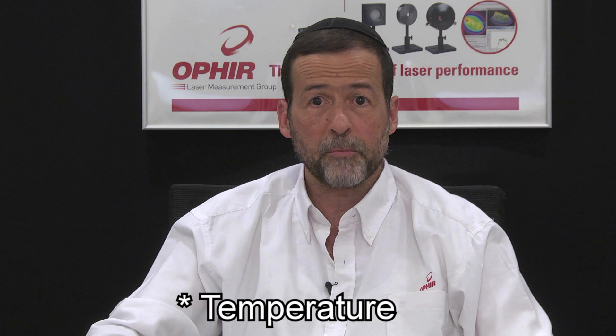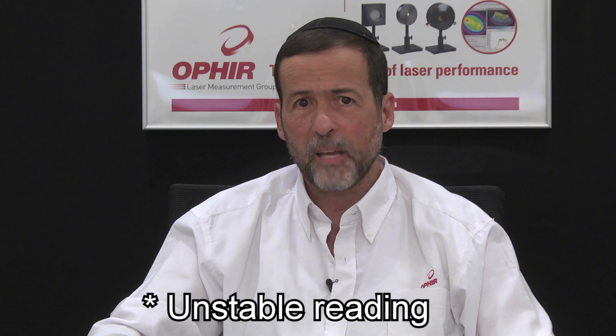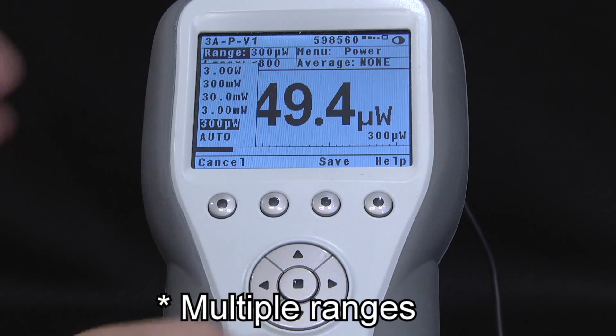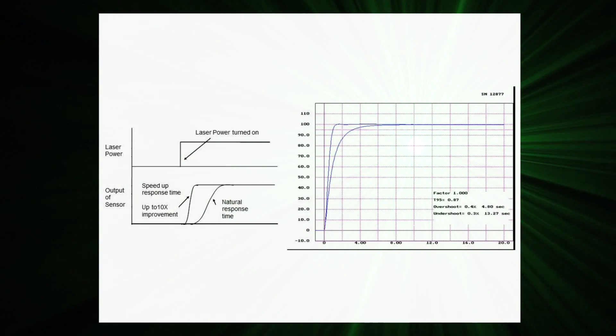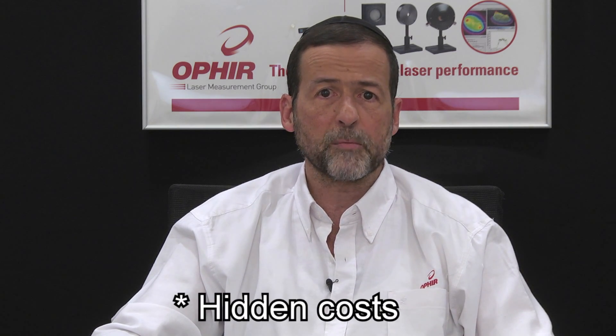The solution will have to correct for the photodiode's dependence on temperature and frequency. It'll have to account for batch-to-batch variations among the detectors themselves. What happens when the reading isn't stable? What about when you need to change gain in real time to give your sensor a useful dynamic range? For certain types of detectors, how about a speed-up algorithm to reduce the response time? Addressing these issues will involve costs, which, though not visible on a system BOM, are nevertheless there — and such hidden costs can be higher than one might think.